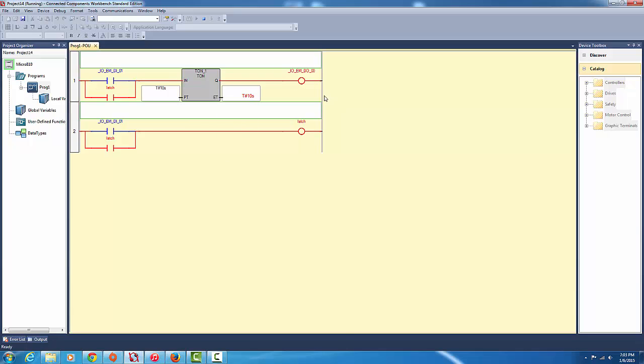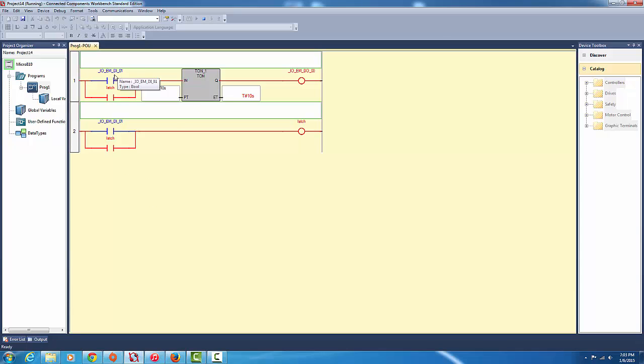Okay so the only problem with the TON is that it doesn't have a reset. And the way the TON resets is if you take power off it. Okay just say you want to take power off it, you create another, you create either emergency stop on the back, normally open on the back, or normally closed on the back which you just press, releases it, and then yeah it starts to cycle all over again. As soon as you take power off the IN, elapsed time will go back to zero seconds.